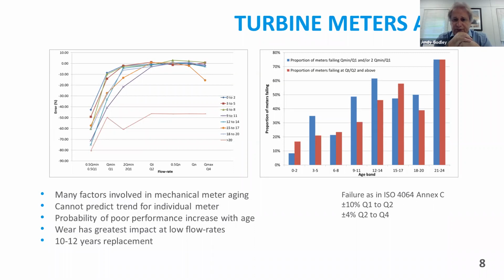We tend to say that around the 10 to 12 year mark is when you should be replacing district meters, because that's when your failure rate is probably around a third. So you've got a 30% chance of a meter failing. And the problem is you don't know which meters they are necessarily. So when you start looking at the economics of it, for every 3 meters you're going to get one that has failed. So the economics, and the risk of poor performance and poor accuracy, balance out around that point. Certainly that's our experience in UK terms.